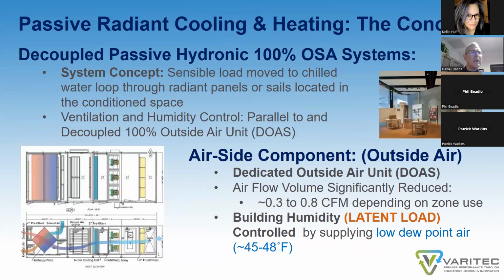Ventilation and humidity control is parallel to and decoupled from the passive radiant system. It is your 100% outside air unit that will control the humidity in the space by supplying air at an adequate enough dew point to absorb the moisture buildup in that building. So the airside component uses a 100% outside air unit. There's no return air back to the building.